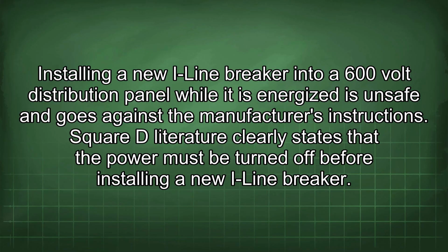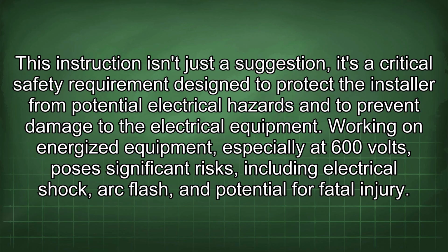Installing a new I-Line breaker into a 600-volt distribution panel while it is energized is unsafe and goes against the manufacturer's instructions. Square D literature clearly states that the power must be turned off before installing a new I-Line breaker. This instruction isn't just a suggestion, it's a critical safety requirement designed to protect the installer from potential electrical hazards and to prevent damage to the electrical equipment.